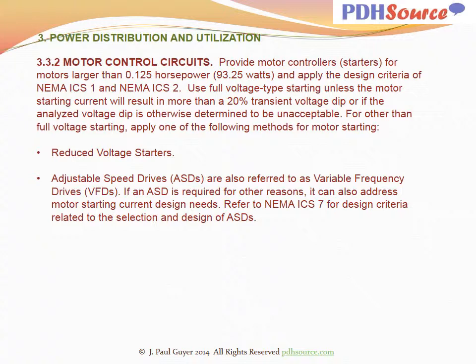Provide motor controllers, starters, for motors larger than 0.125 horsepower and apply the design criteria of NEMA ICS1 and NEMA ICS2. Use full voltage type starting unless the motor starting current will result in more than a 20% transient voltage dip or if the analyzed voltage dip is otherwise determined to be unacceptable. For other than full voltage starting, apply one of the following methods for motor starting: reduced voltage starters.